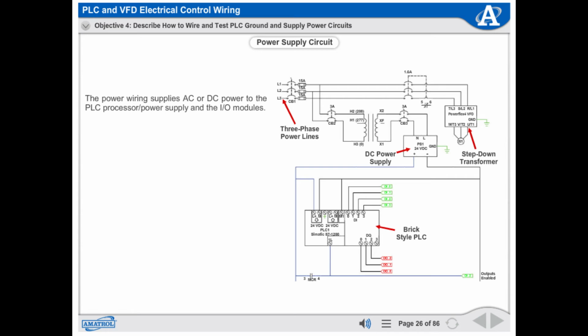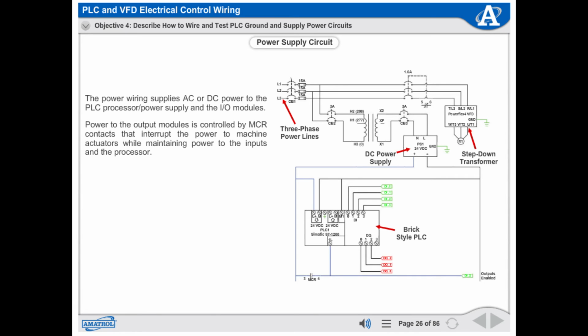The power wiring supplies AC or DC power to the PLC processor power supply and the I/O modules. Power to the output modules is controlled by master control relay contacts that interrupt the power to machine actuators while maintaining power to the inputs and the processor. The specific wiring depends on the PLC style, brick or chassis, and the PLC power required, AC or DC.